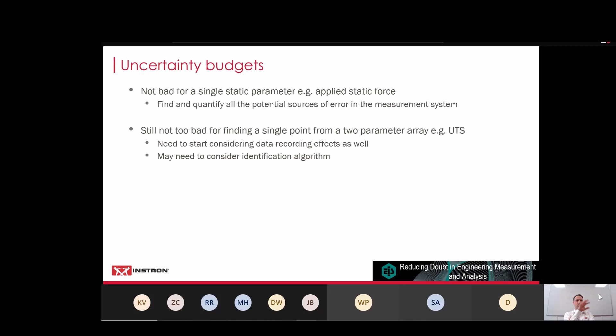If we're finding a single point from a two-parameter array, so let's take the example of just finding the ultimate tensile strength, which is going to be the peak force if we just slowly stretch our specimen until it goes snap. We can express that as a two-parameter array of force versus displacement, stress versus strain, I should say, or even stress versus time. Just find the maximum. You do need to start considering those data recording effects which I was talking about, and you might need to consider the search algorithm that's finding where the highest one is. But again, it's not looking too bad.